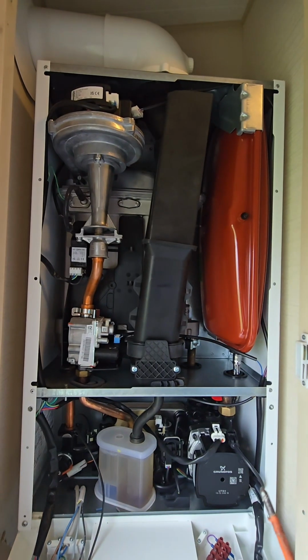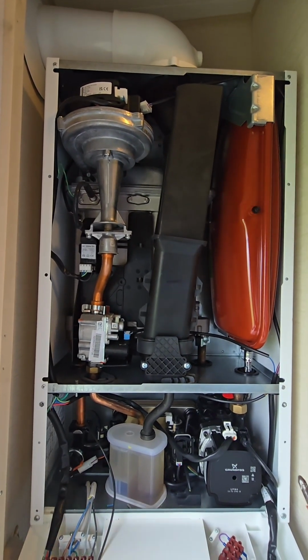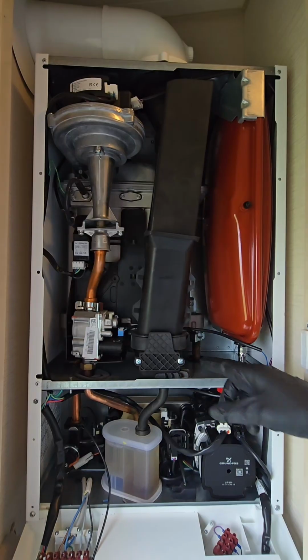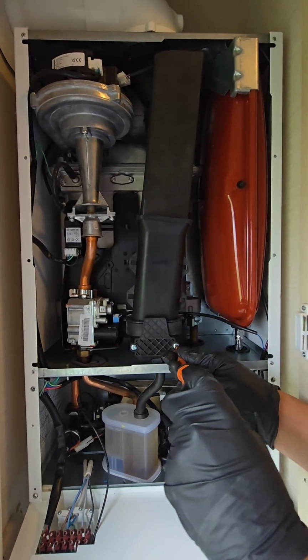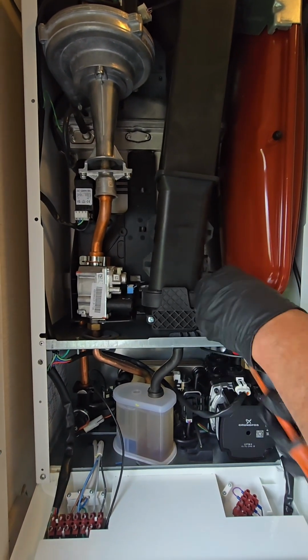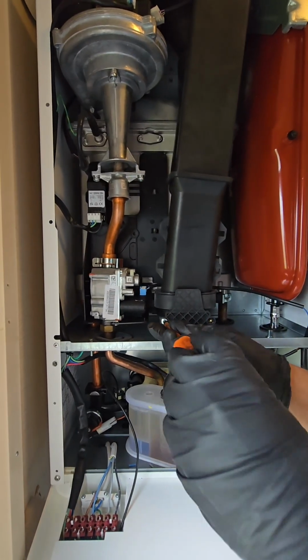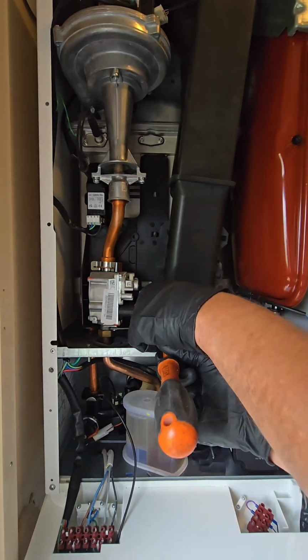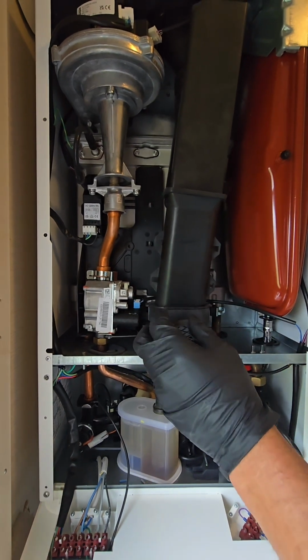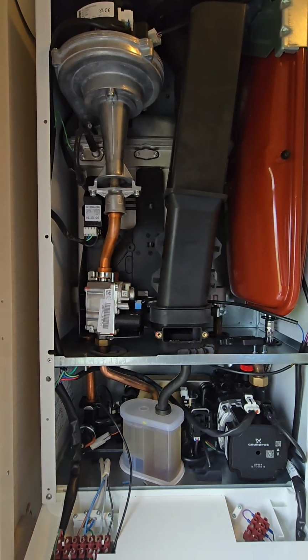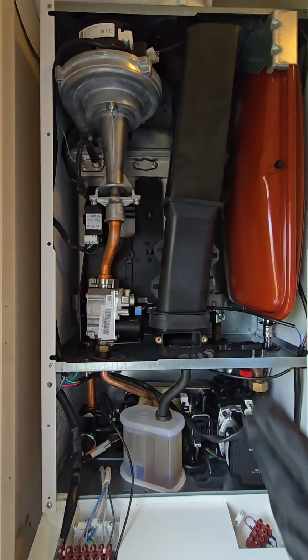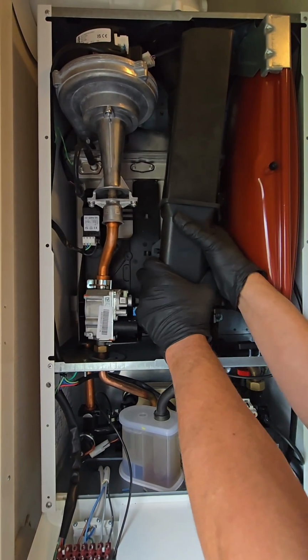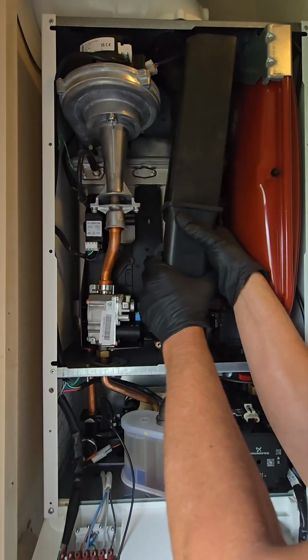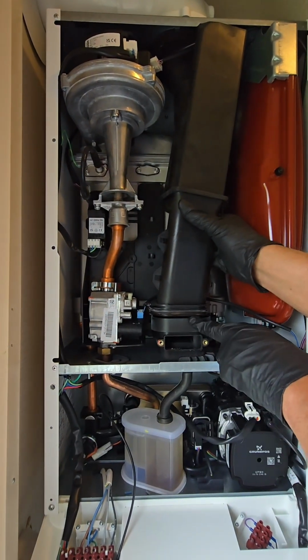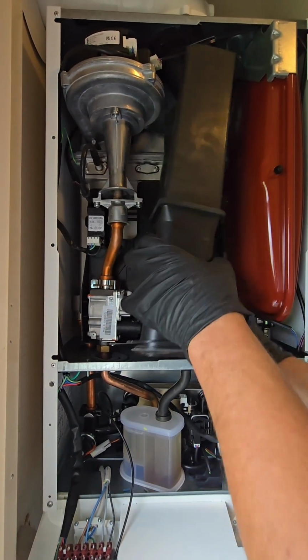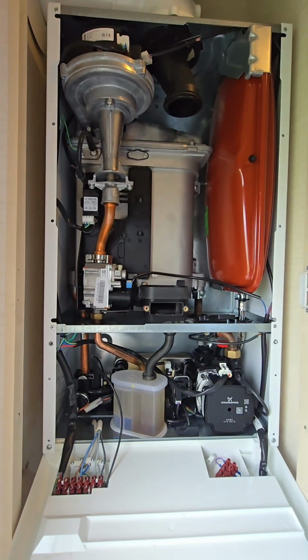And now we're going to start stripping the appliance down and cleaning out the heat exchanger. So first of all, undo the 2 sump screws, put them to one side. Remove the sump cover. Then with 2 hands, grab hold of the flue manifold, wiggle it up in the air until it releases from here. Bring it out, wiggle it down and put it to one side.